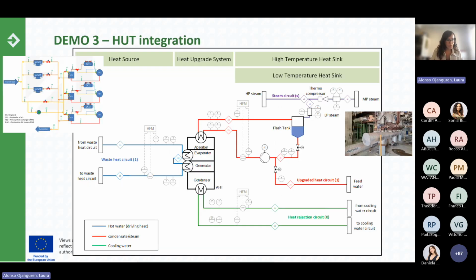Okay, here is a presentation of how the system is integrated with the different streams connecting with the plant. So this is the waste heat recovery circuit, which Abdel explained before. This will share the waste heat to the compression heat pump and to the heat transformer. In the heat transformer, we take the waste heat in the evaporator and generator in series. Then in the condenser, we are rejecting at a low temperature level, at around 15 to 20 degrees. And we upgrade the heat in a water stream at around 145 degrees.